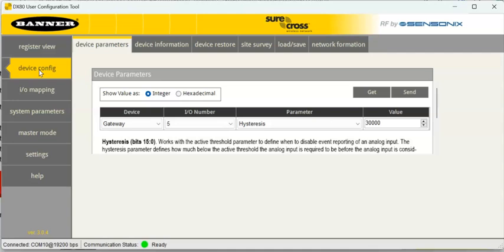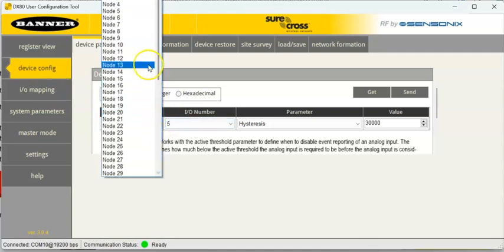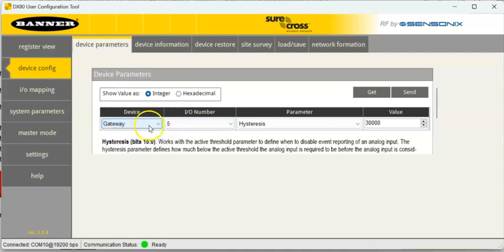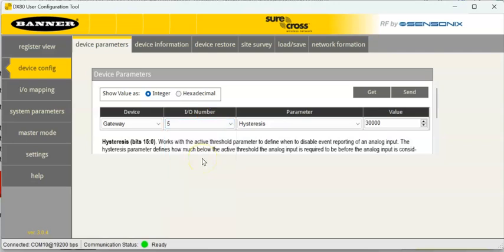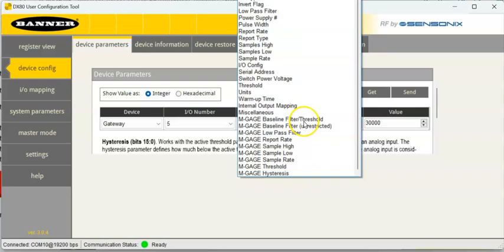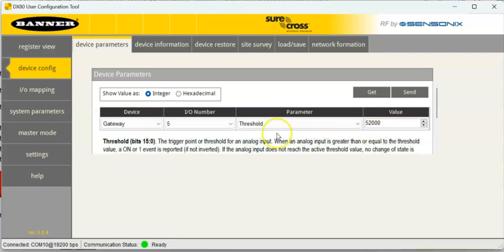We'll go here to device configuration. I'm using analog input 5 on here for my 0 to 20 milliamp sensor, and I've set up three things on that particular IO point. So, if you hit the pull down here, you can select the gateway, and then your IO number. I'm looking at number 5, and there's three things I'm setting up. The first thing I'm setting up here is the threshold. I've got the threshold here set to 52000. Remember, I'm using analog sensor, so it's going to go from 0 to 65,535 over the range of 0 to 20 milliamps.